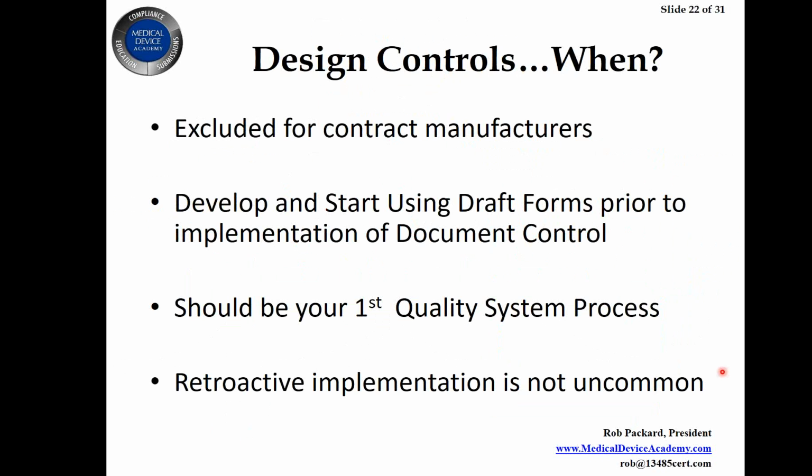You want to be training people, make sure they're competent in design controls and risk management, because you don't want to have to create a bunch of things retroactively and find out you have to redo things because you didn't do it correctly. So usually I'll implement a lot of the forms for design controls in a startup company before we even have a procedure for design controls.